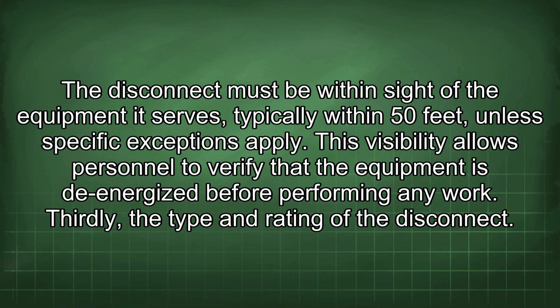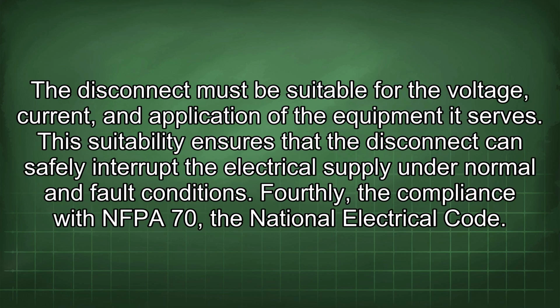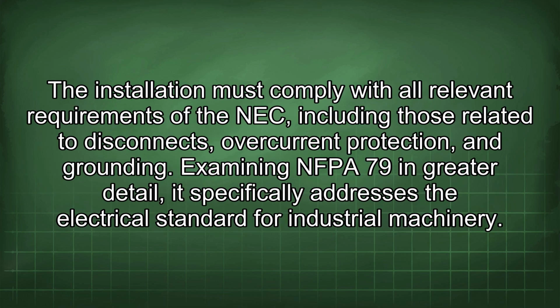Thirdly, the type and rating of the disconnect. The disconnect must be suitable for the voltage, current, and application of the equipment it serves. This suitability ensures that the disconnect can safely interrupt the electrical supply under normal and fault conditions. Fourthly, compliance with NFPA 70, the National Electrical Code. The installation must comply with all relevant requirements of the NEC, including those related to disconnects, overcurrent protection, and grounding.